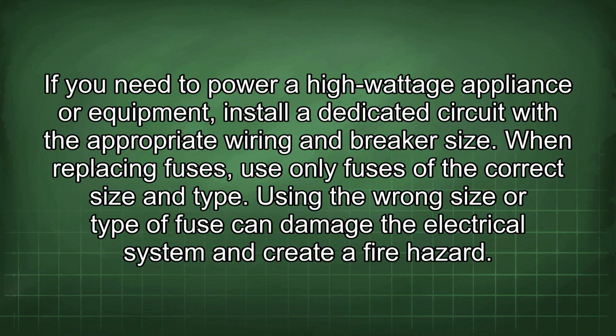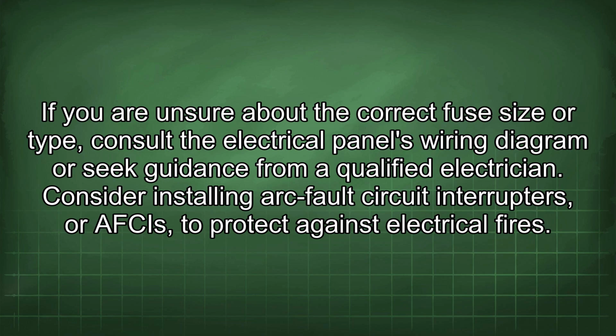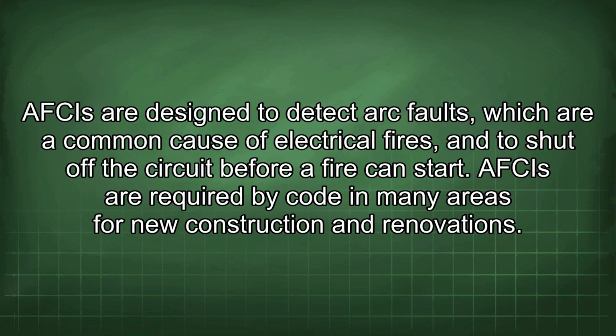Using the wrong size or type of fuse can damage the electrical system and create a fire hazard. If you are unsure about the correct fuse size or type, consult the electrical panel's wiring diagram or seek guidance from a qualified electrician. Consider installing arc fault circuit interrupters, or AFCIs, to protect against electrical fires. AFCIs are designed to detect arc faults, which are a common cause of electrical fires, and to shut off the circuit before a fire can start.